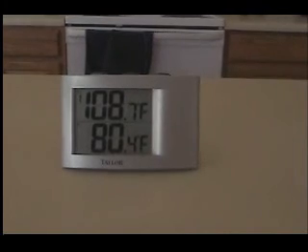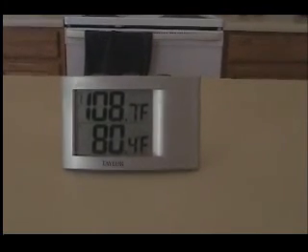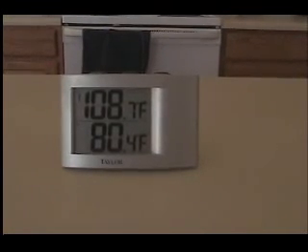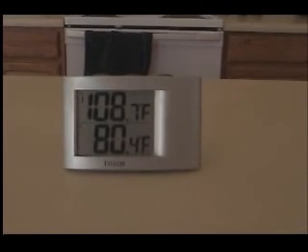The next step is to set a thermometer someplace in the middle of your house so you can record the results. So this thermometer is saying that it's 108.7 outside and 80.4 inside. Now the next thing we'll do is turn on the air conditioners. This house has two ACs, so there's two thermostats. First one is digital, it's showing 80 degrees, and so we just lift the cover, turn on cool, and that air conditioner will come on. The second thermostat is still an old Mercury mechanical, and you can read it, and it says it's just under 80 degrees. And so we're going to turn that cooling system on.